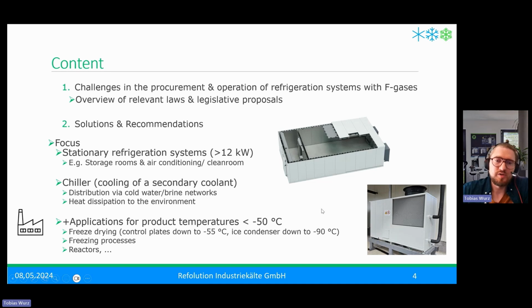Since we're experts in ultra low temperature, we have an extra chapter, an extra view on applications for product temperatures below minus 50 degrees. If you're familiar with the F-gas regulation, in the old version we had an exemption for minus 50. Something happened, or will happen, with that exemption, but I'll talk about it later. Applications with these low temperatures are, for example, freeze drying, where you have different stages at the plates of minus 55, and at the ice condenser where you get the ice from your pharmaceuticals you want to suck out at minus 90, the lowest we know. You also have freezing processes, reactors, and a lot of applications that are not that common in the normal refrigeration world.